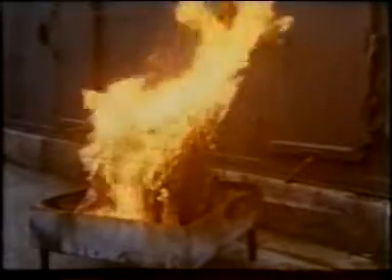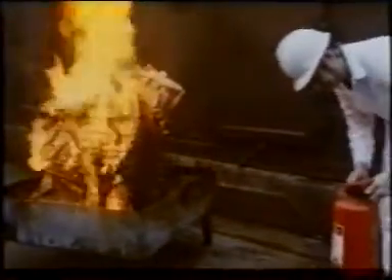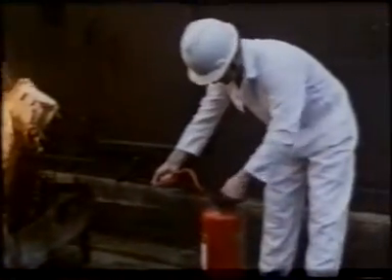The apparatus is very suitable for dealing with fires involving flammable solids of the carbonaceous category, such as wood, paper, bedding, curtains, the sorts of things you see when you look around the average mess room or cabin. These fires can quickly become deep-seated, and water has the advantage of penetration, which aids the effect of extinguishing by cooling.